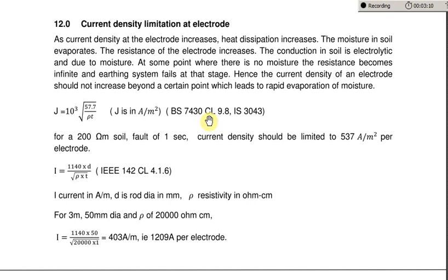Now you have to observe one thing here. What does this 537 amps per meter square mean? Suppose you have a fault level of 40 kA. The actual fault may be around 30 kA, and all of this 30 kA does not enter the neutral through the earth electrode — only some portion enters through the earth electrode. So the fault current which enters the earth only flows through the earth electrode, and we may need around 2 to 4 earth electrodes connected to the neutral.